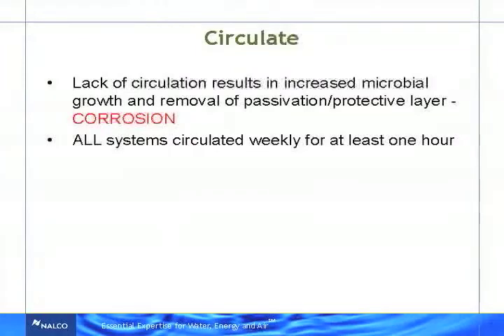Second thing, and really if I was going to rank these five as to what's the most important, this should be number 1. It's just chronologically it's usually number 2. Number 1 is circulation. I can't stress enough that you need to circulate your system. Lack of circulation results in corrosion. You get cells forming where the corrosion inhibitors that are in the water can't reapply. You also get biogrowth sitting in stagnant water, which, like Mike talks about, has acid waste, which then causes pinhole leaks and things like that. So lack of circulation is the number 1 cause of corrosion.